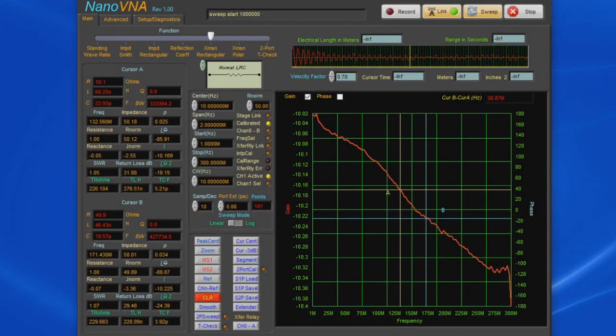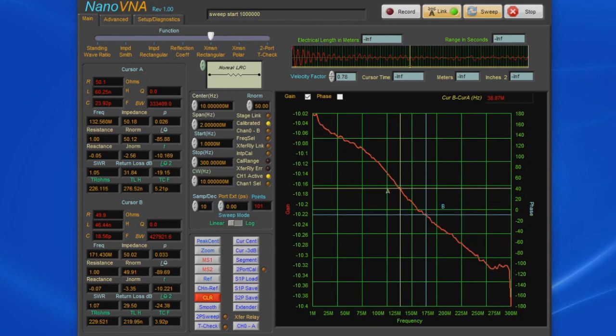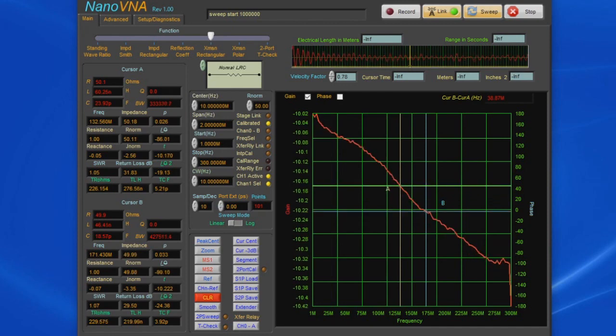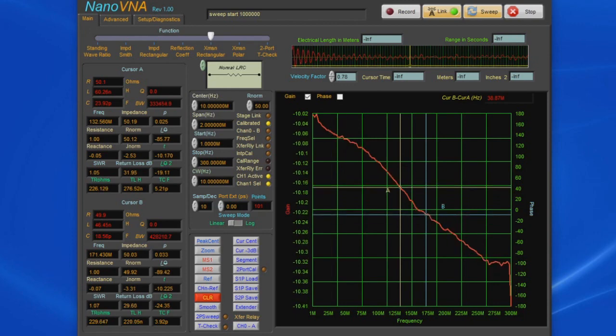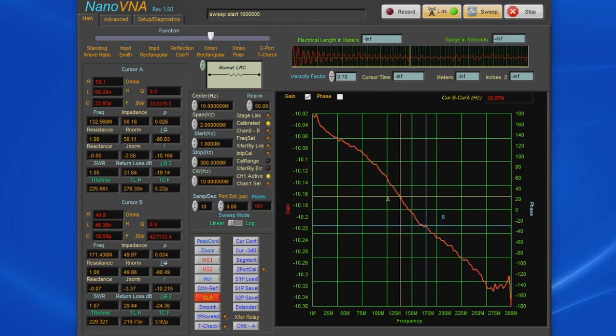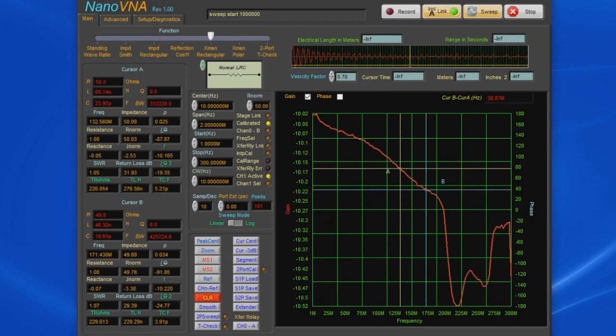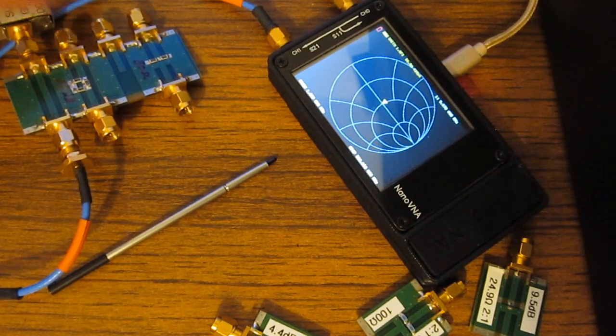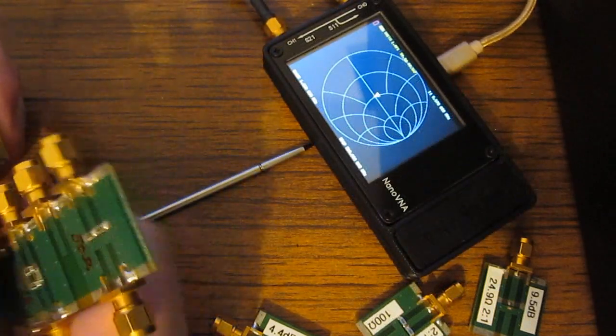So it looks like it starts out at roughly 10.02, and it gets as low as about 10.5 or so dB. Fairly flat up to 300 megahertz. It's not very important because, again, the plan is to basically calibrate out any errors that this is going to create. So the way that we do that is we just run through a normal calibration.